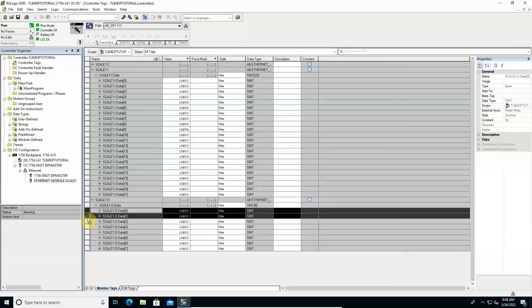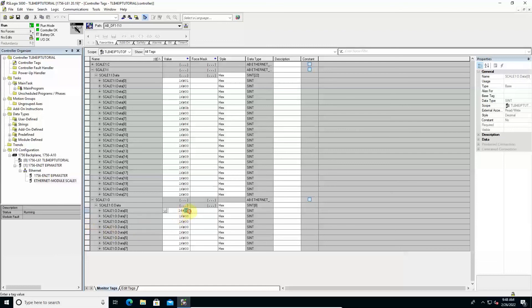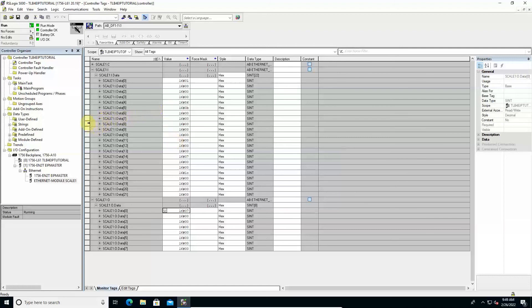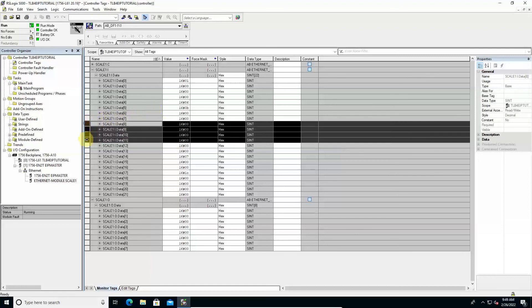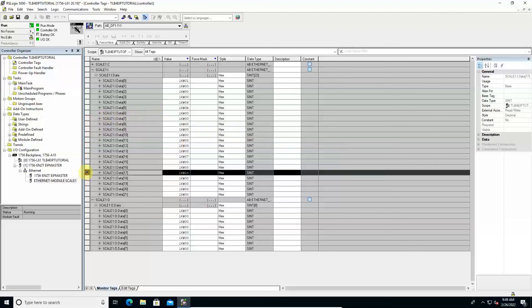Considering the little endian notation currently applied, by writing the code 7 in the least significant byte of the command register, a semi-automatic tare operation is required. Once executed the net weight is zeroed and bits 10 and 11 of the status register changed to 1, signaling an applied tare and a displayed weight value equal to 0.